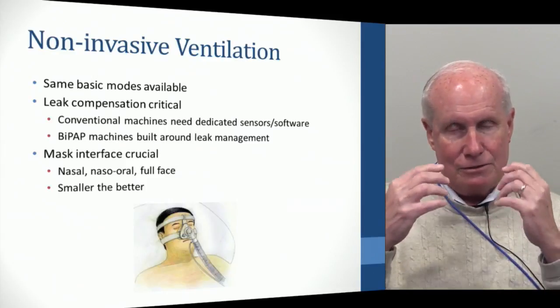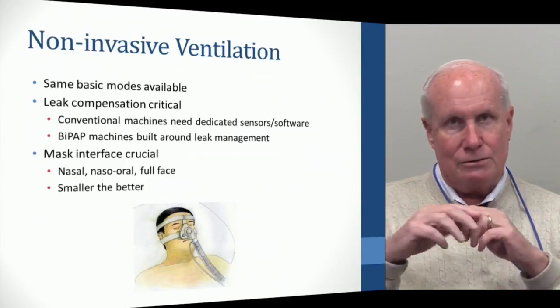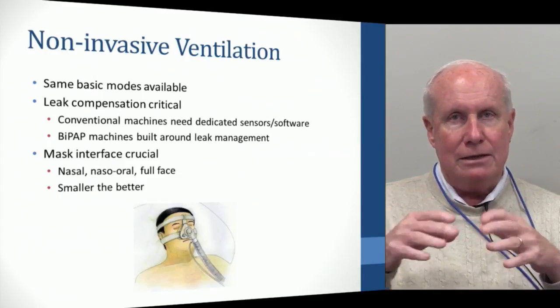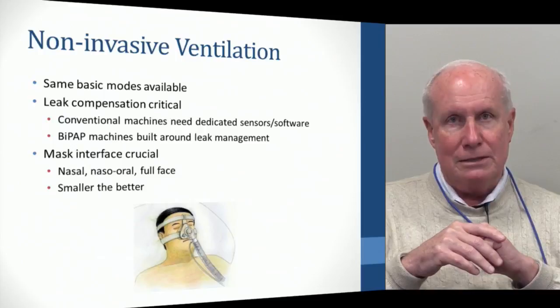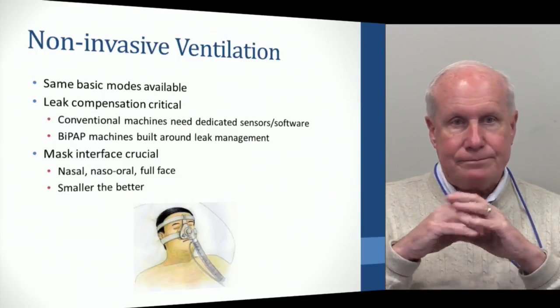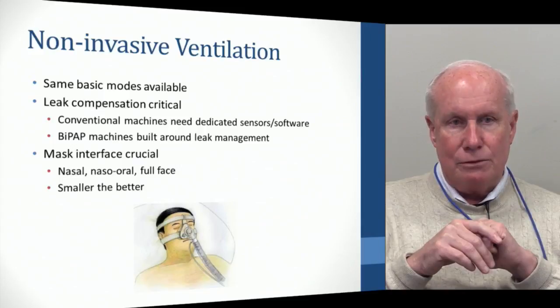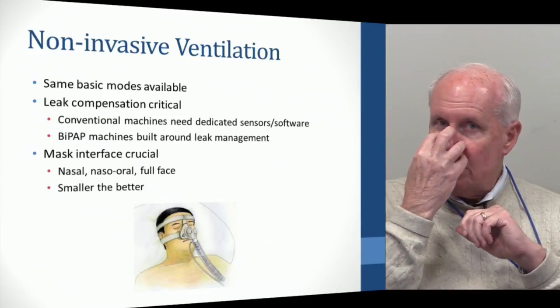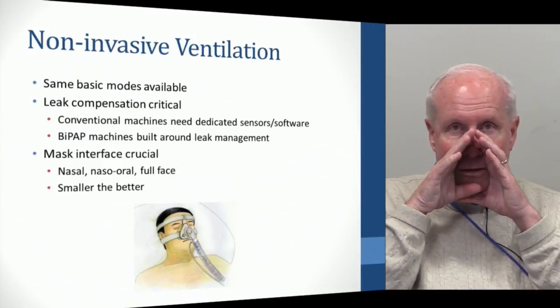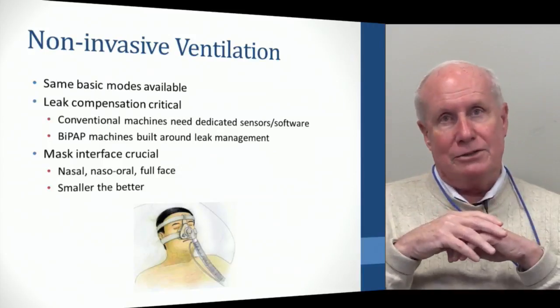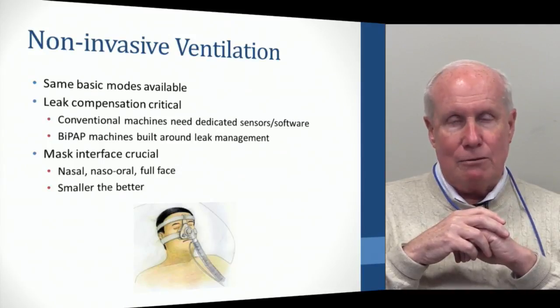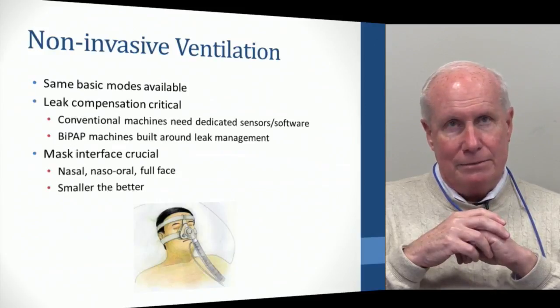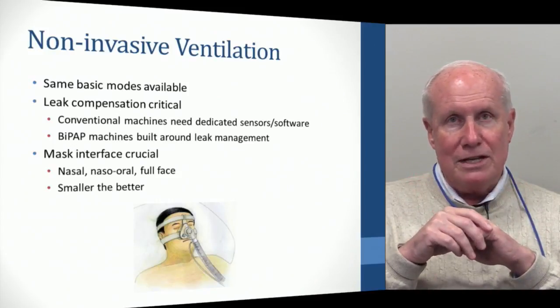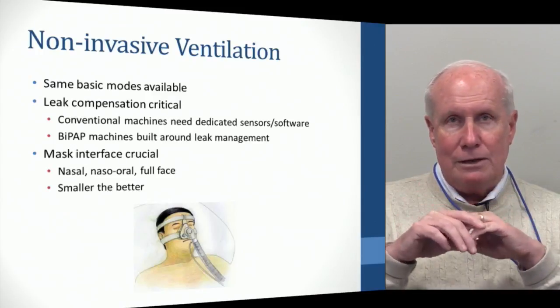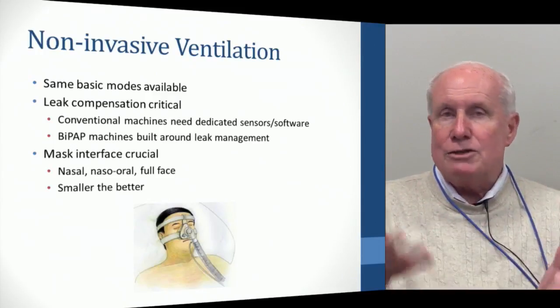That is to say, it's got pressure assist control, pressure support, possibly volume assist control, but it's got the inherent leak compensation mechanisms built in, and it can be used with a mask. The mask interface is absolutely crucial, and they range all the way from nasal masks that just cover the nose to oronasal masks, all the way up to full face masks. And in general, the smaller the mask, the more comfortable it is. But again, the smaller the mask, you may get more intolerable leaks. It may be more difficult to provide the ideal amount of pressure you want to give. So it's a balancing act.